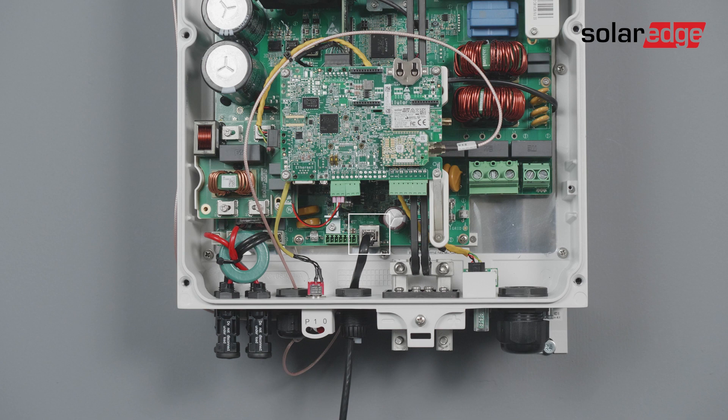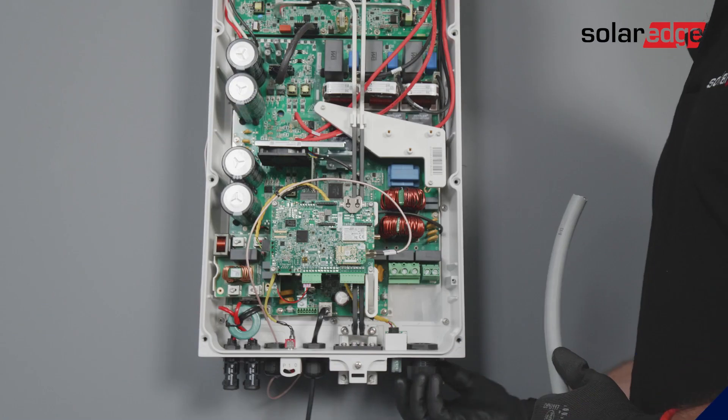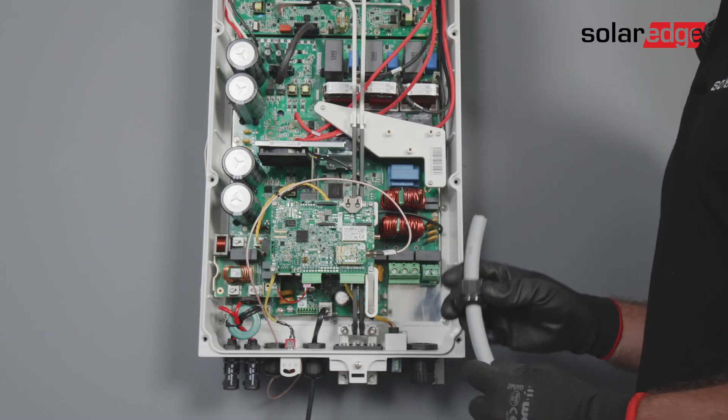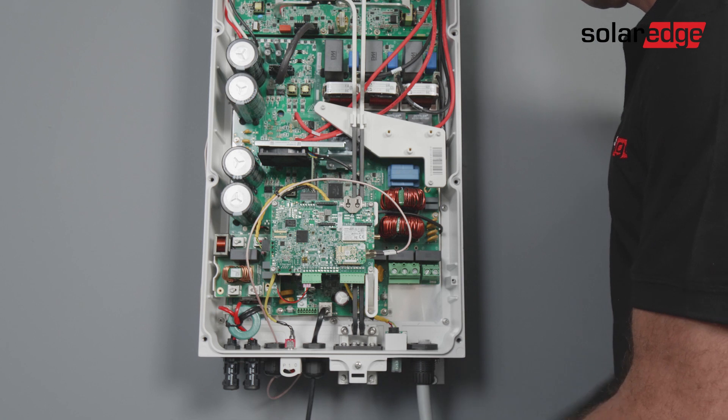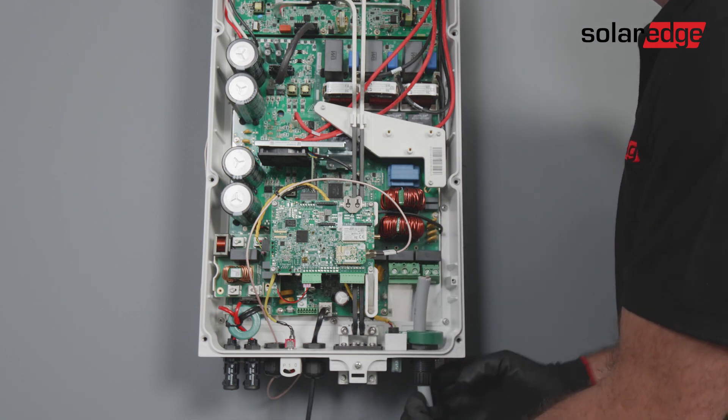Now we move on to learn how to connect the inverter to AC. Use a 5-wire cable. The maximum wire size for the input terminal blocks is 6 square millimeters. Open the AC cable gland. Insert the AC cable through the AC gland. Thread the AC cable through the ferrite bead supplied with the inverter.